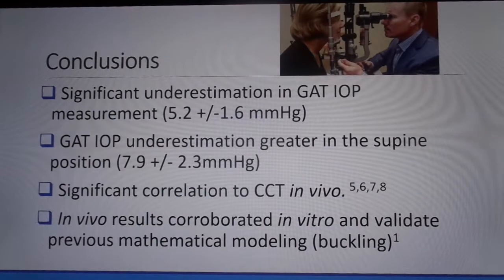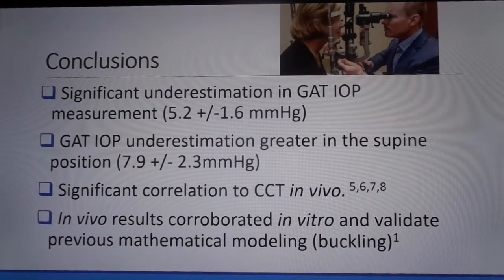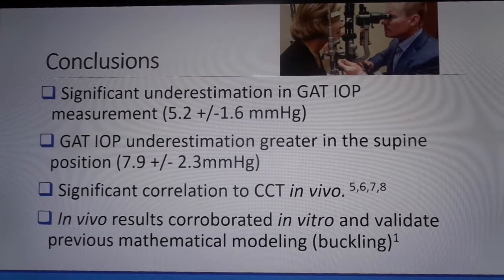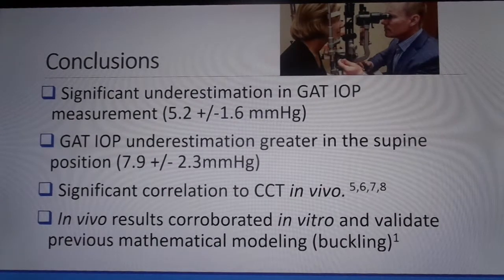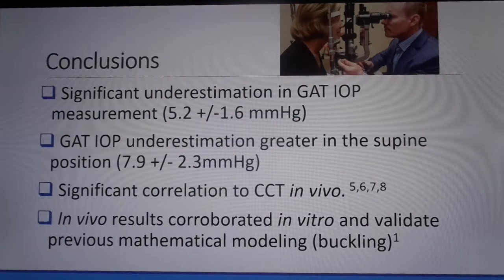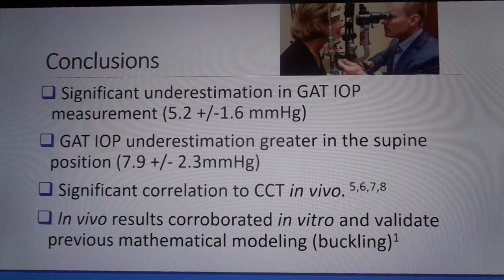The question remains: why does Goldmann underestimate the intracameral pressure? By thin-walled pressure vessel theory, in an infinitely thin membrane cornea, the Imbert-Fick law would apply exactly. Any increase in corneal thickness would only add force to the tonometer, creating an overestimation in intraocular pressure. We believe the discrepancy was demonstrated in our mathematical modeling published in Translational Vision Science and Technology, which showed a central corneal buckling when the surface was applanated flat. Due to the buckling, the central cornea adds almost no appositional force to the tonometer prism face.